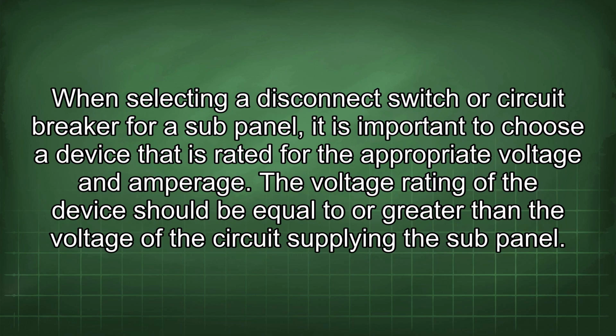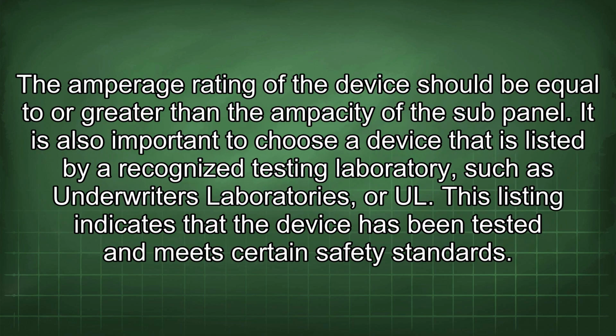When selecting a disconnect switch or circuit breaker for a sub-panel, it is important to choose a device that is rated for the appropriate voltage and amperage. The voltage rating of the device should be equal to or greater than the voltage of the circuit supplying the sub-panel. The amperage rating of the device should be equal to or greater than the ampacity of the sub-panel.